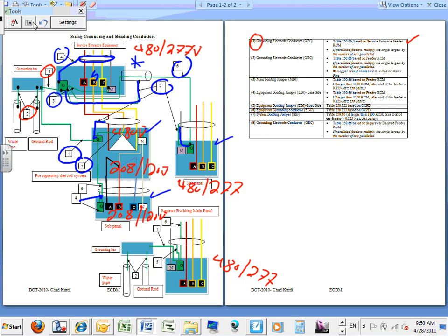Some of them, like for example, do I need an equipment grounding conductor if my conduit is EMT or metallic? No. But if you need it, this is how you size it. Let's take an example right away. Let's take a 4,000 amp switchgear.